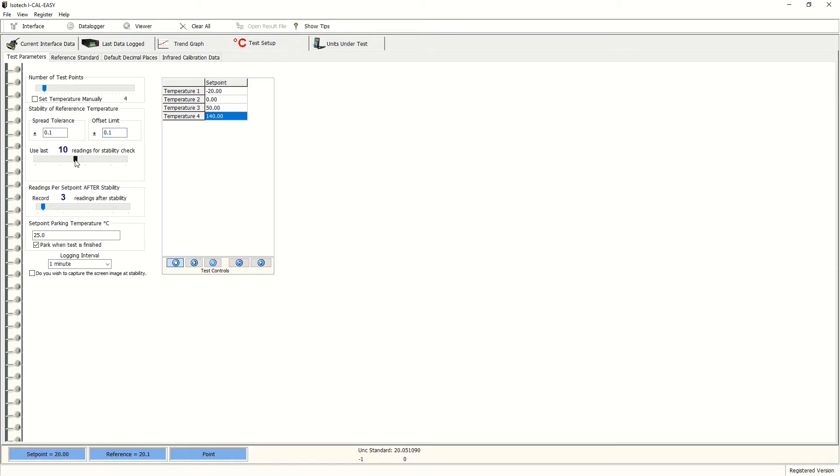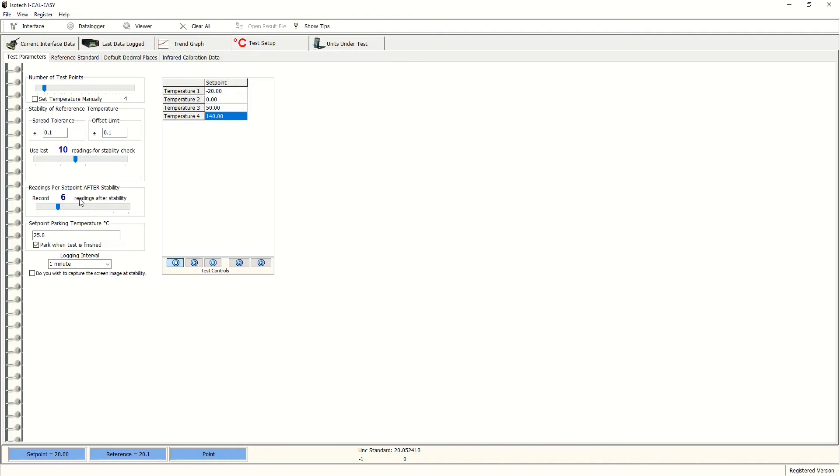And then once we've reached stability and the test has repeated within that tolerance 10 times, we can then decide to take up to six readings, for instance, and average these to produce the result for that temperature before proceeding to the next temperature point.